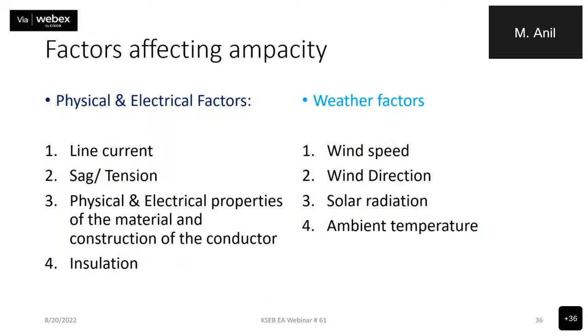So, factors affecting the ampacity: physical and electrical factors, line current, sag, tension, physical and electrical properties, the material of the conductor and construction of the conductor, then insulation. And weather factors: wind speed, wind direction, solar radiation, ambient temperature, etc. So if the ambient temperature drops at the site where the line is situated, then we can load the line more. So we need to have sensors at different points along the line to capture the temperature, wind speed, wind direction, etc. To the system operator, that is the transmission system operator or load dispatcher, and the load dispatcher can decide upon the enhanced loading capacity to contain the sag or tension of the line at appropriate levels.